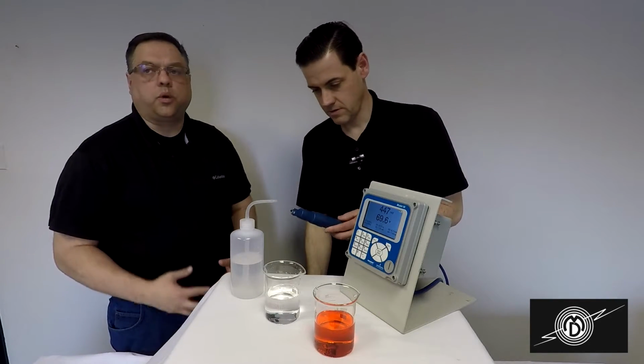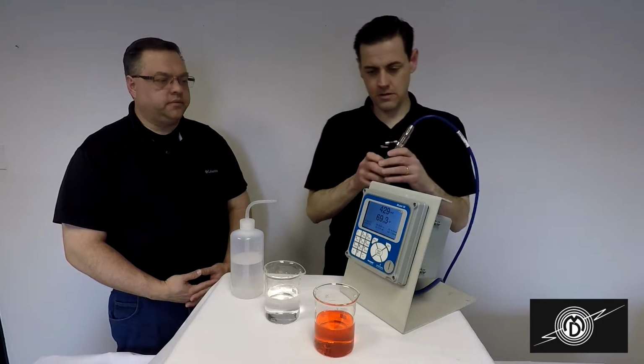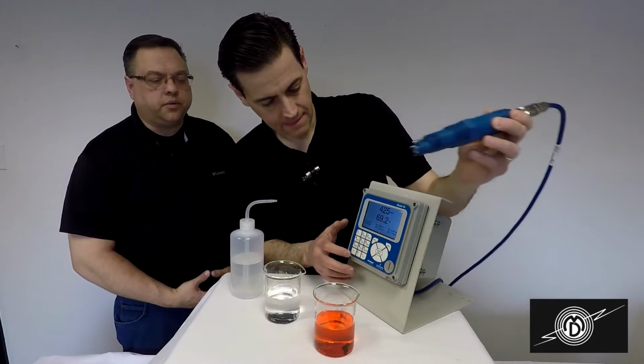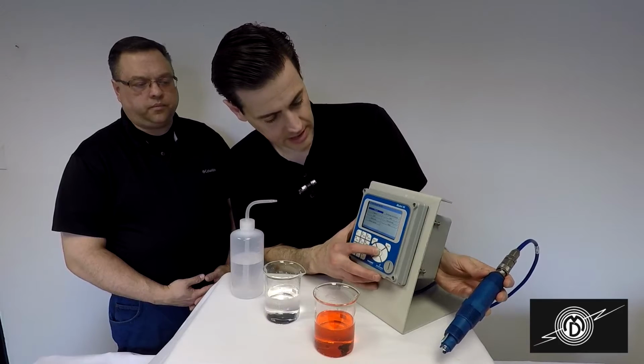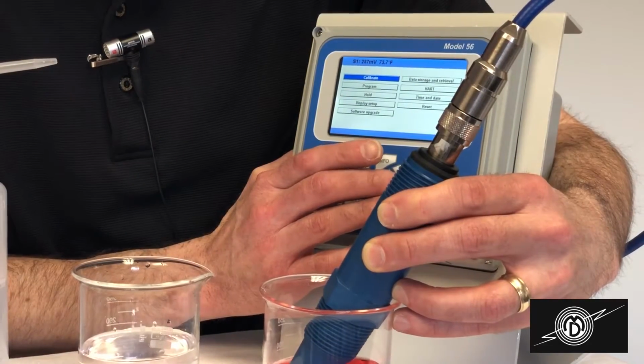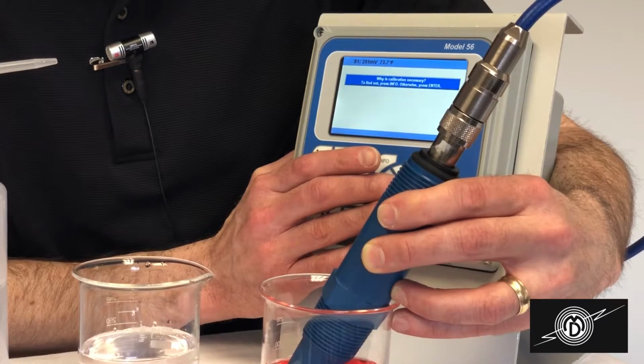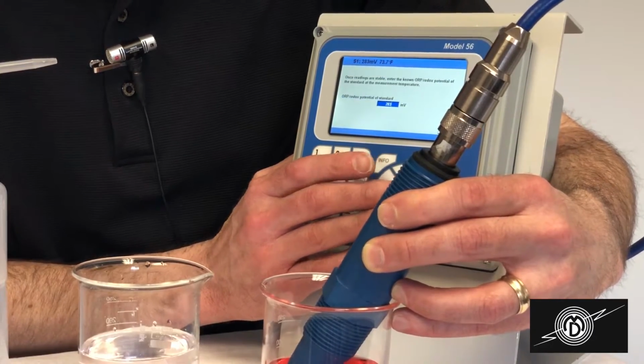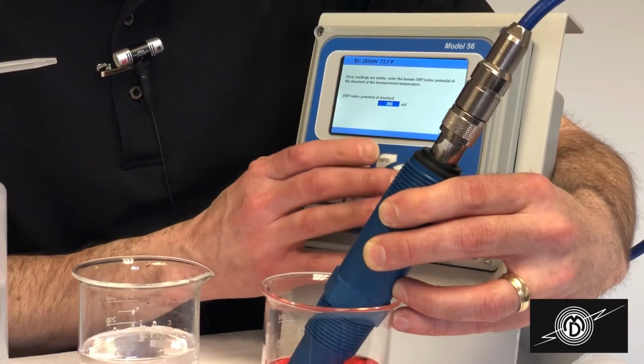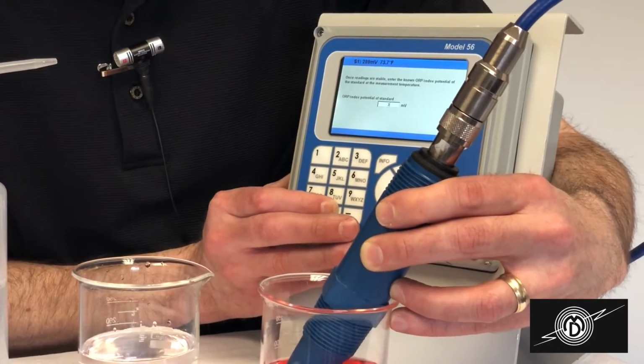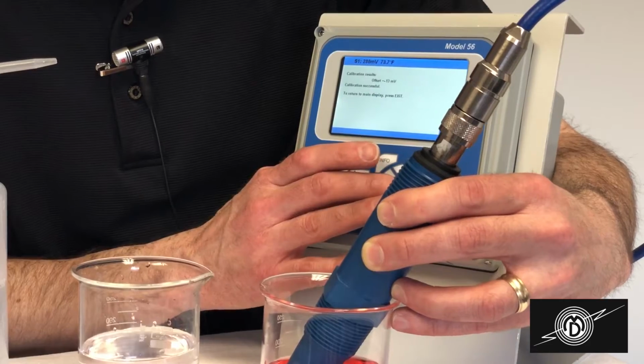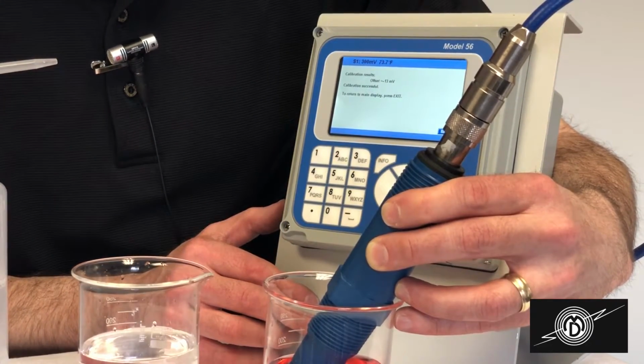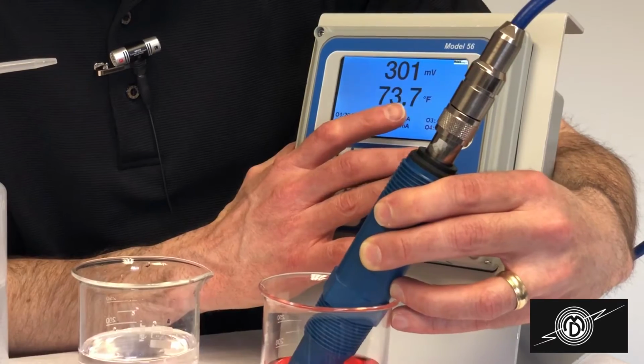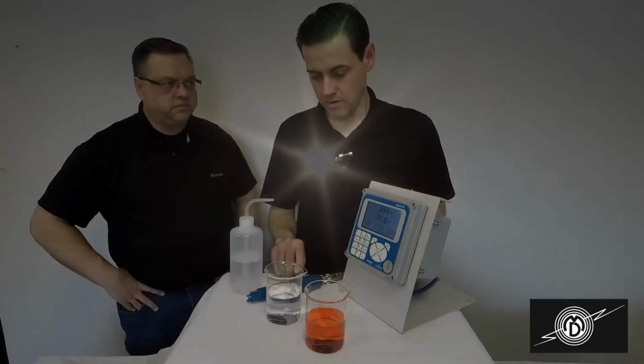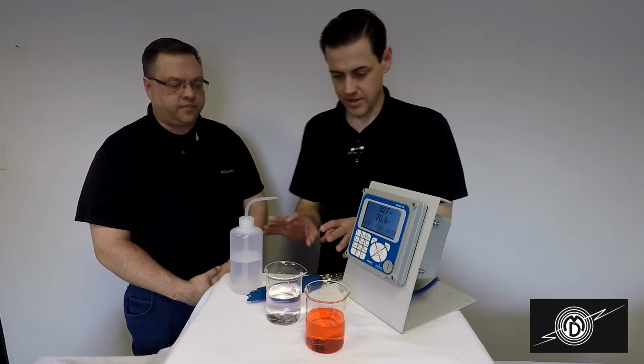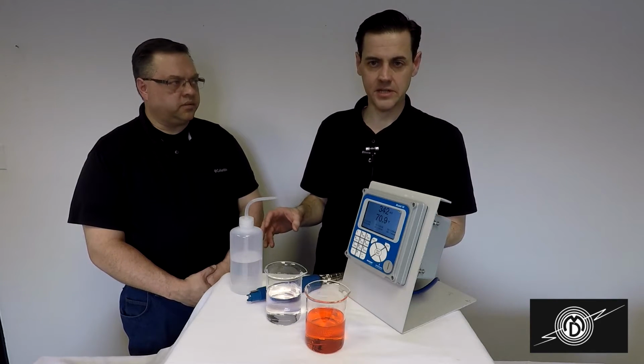And then you can place it in your 1-point standard solution. Okay. Allowing it time to adjust to the standard. Okay, so we're going to get into the calibration menu here. And there you have it. So now that we're standardized, the sensor is cleaned and then placed back into the process.